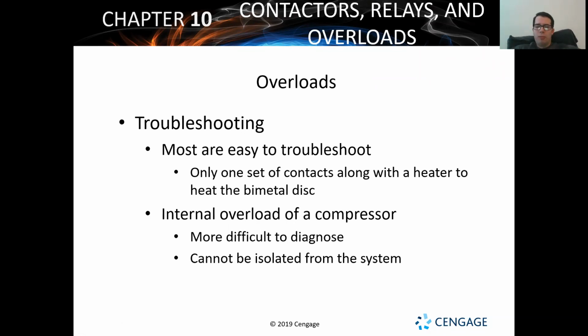All right. So the problem you can have with these that's really easy to misdiagnose is people will say it's a bad compressor. And they'll say it's a bad compressor because they'll check across their windings and they'll read open. They'll read OL or they'll read infinity. And they know, oh, well, I've got an open winding. Then I obviously have a bad compressor, because typically that is the sign of a bad motor. If one winding is open, the motor's shot. It's done.